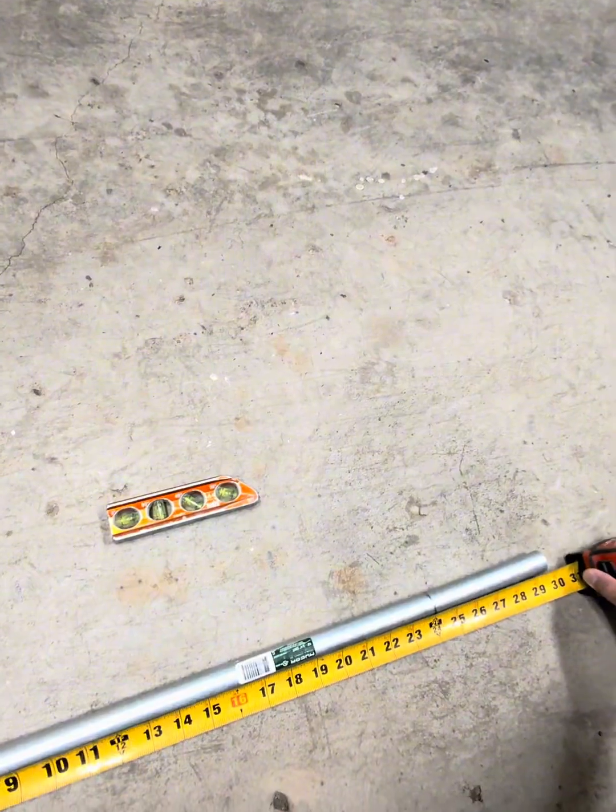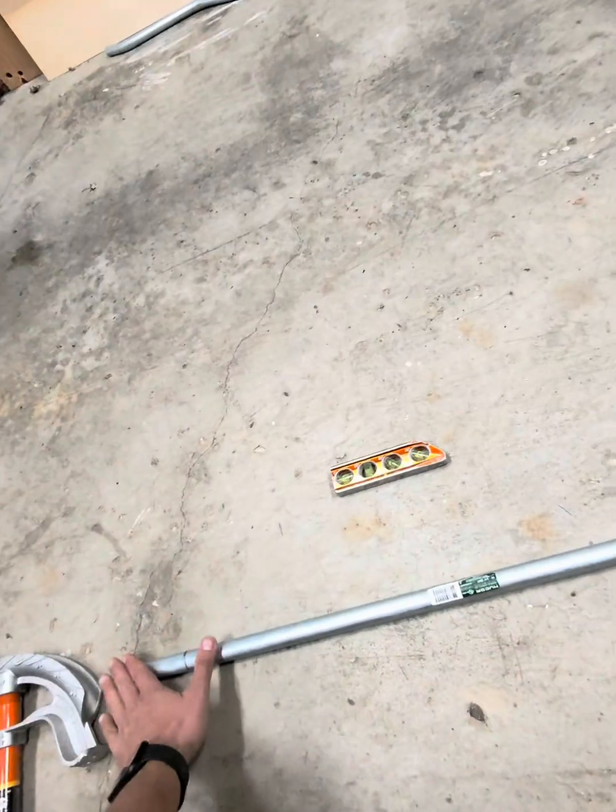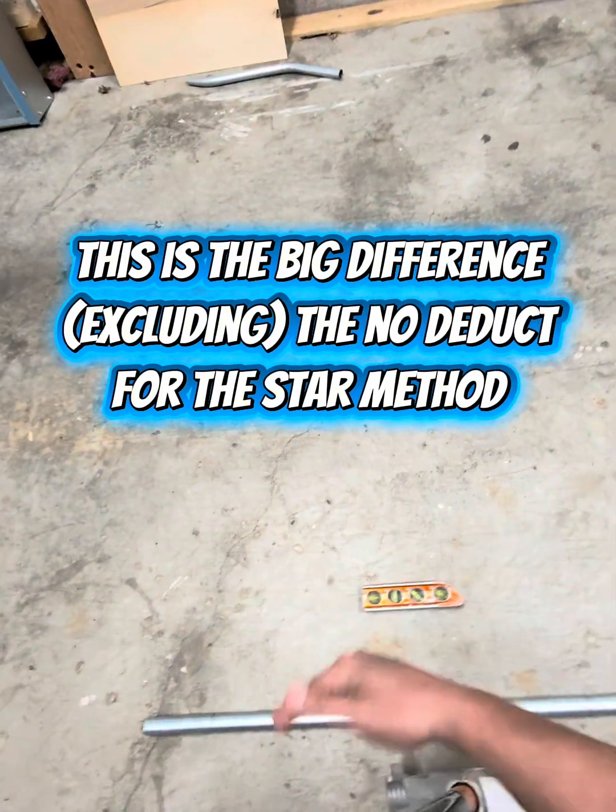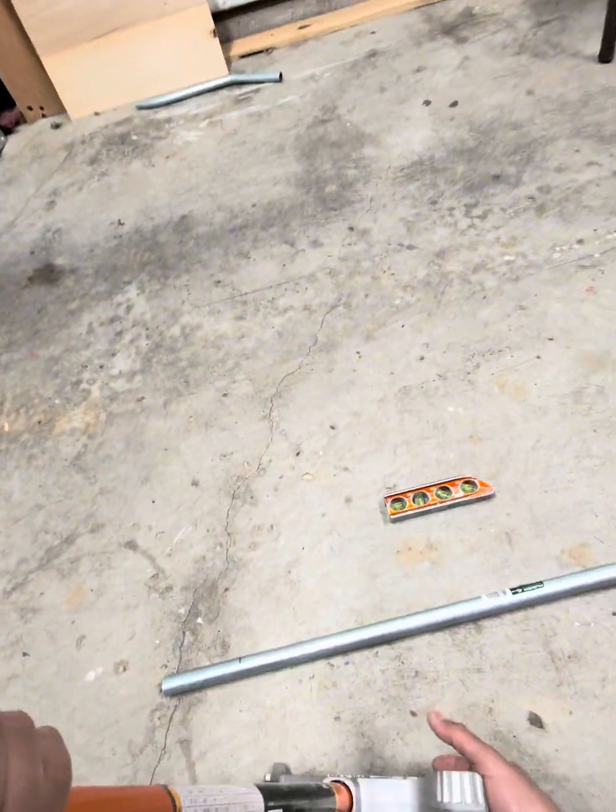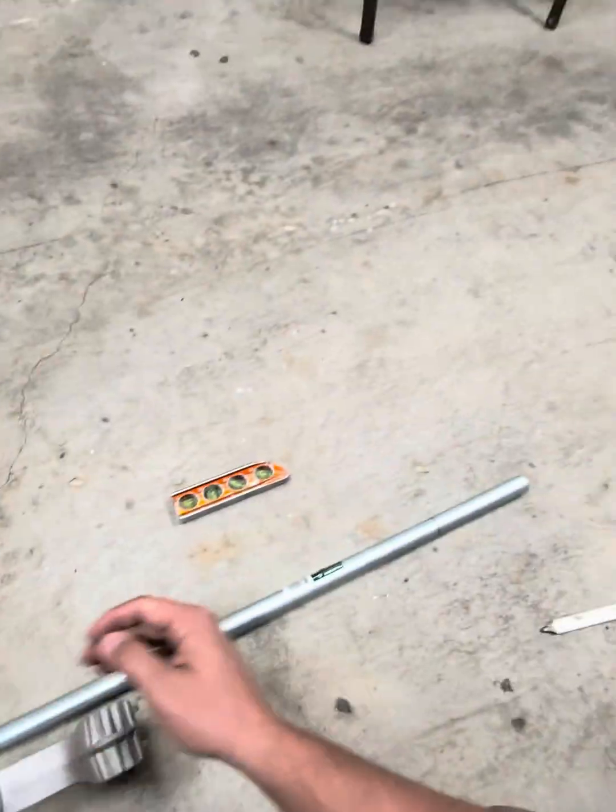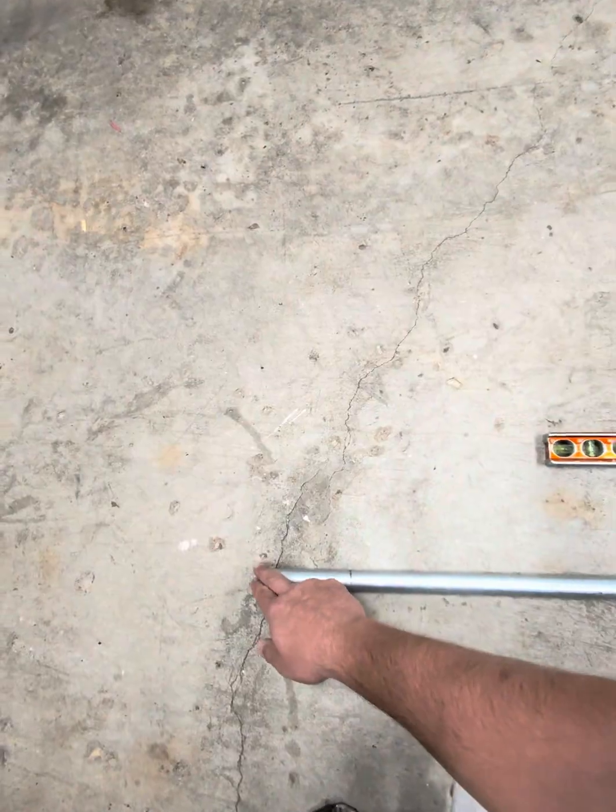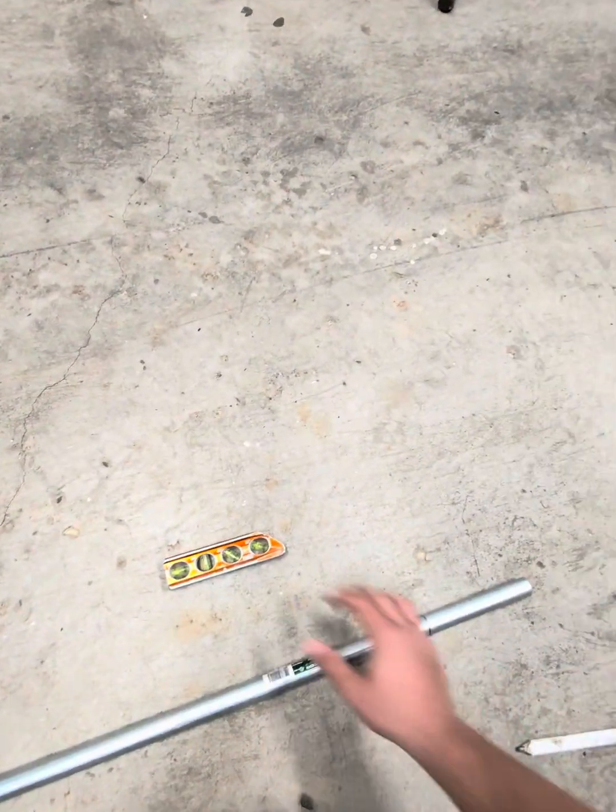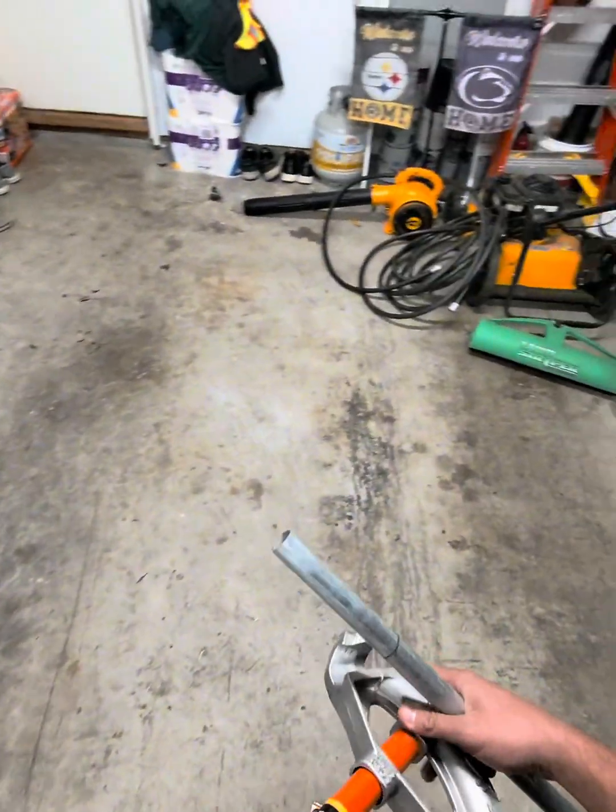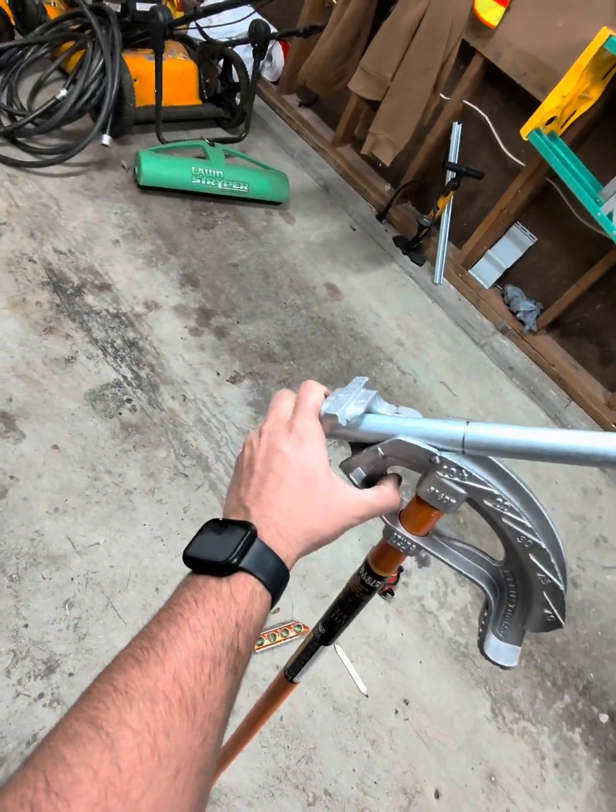With that being said, the first thing we're going to do, 24 inches. We're going to mark that out. I already have it marked 24 inches off the end of the conduit. Now what you would normally do is wherever you make your mark, you're going to face your bender to it. But with the star method, instead of doing the deduct and facing it that way, we're just going to flip our bender around. So we marked it off the end. Instead of facing it from the way our tape measure came, we're going to face it the opposite way.